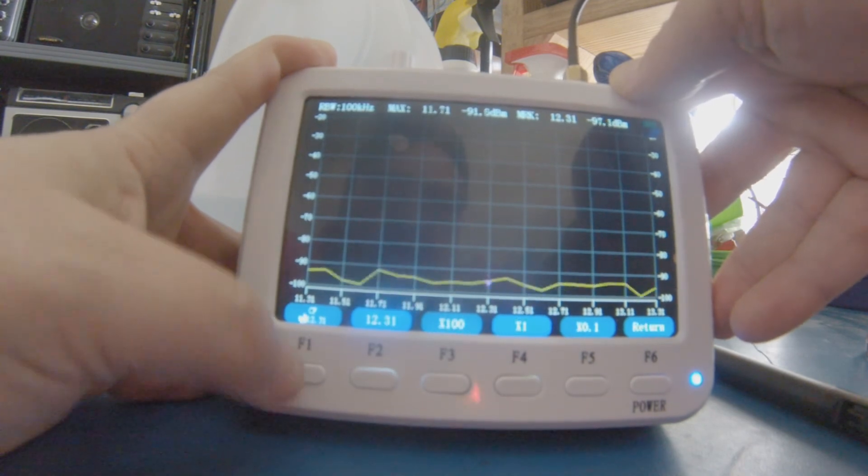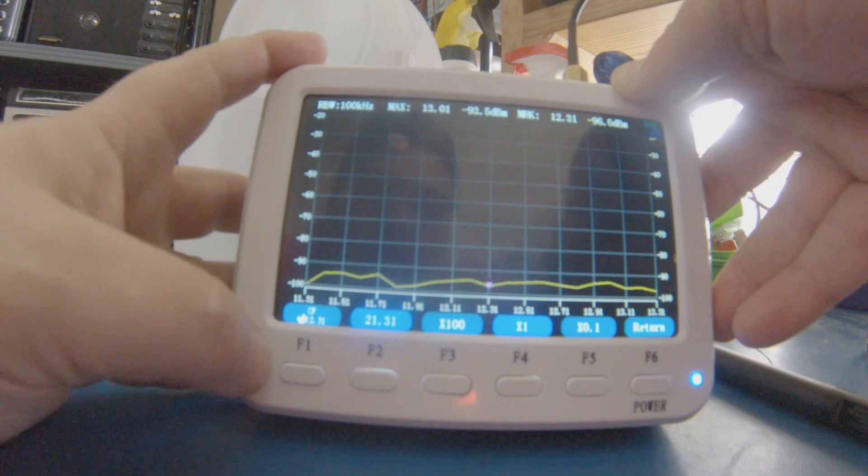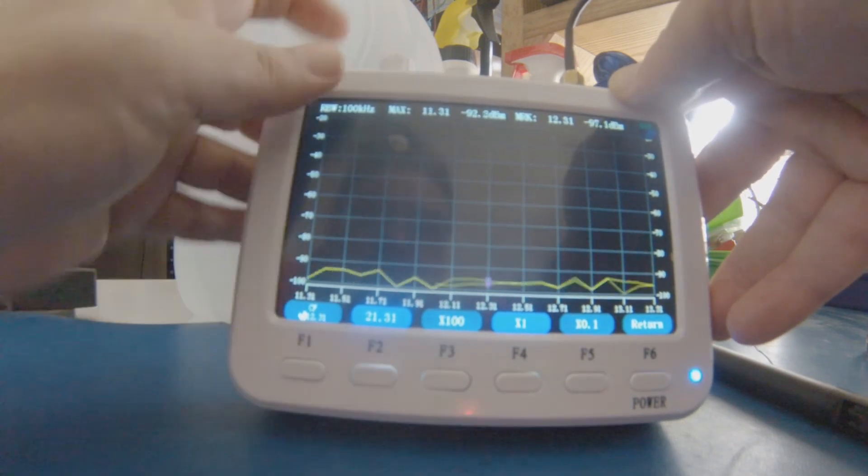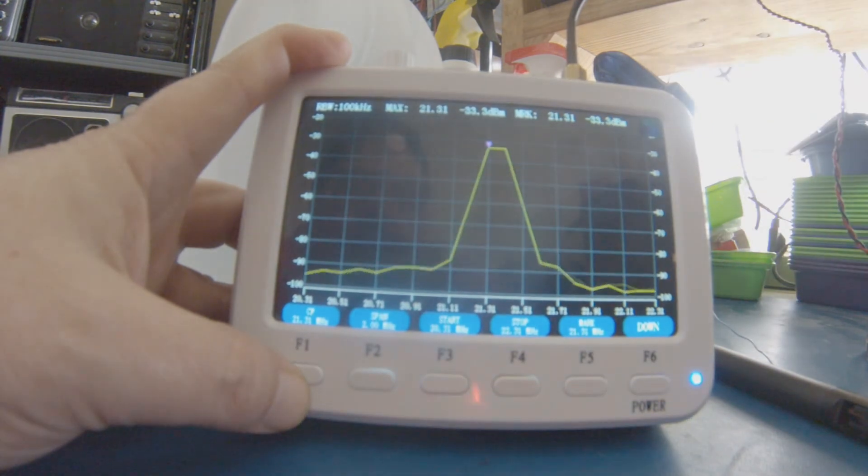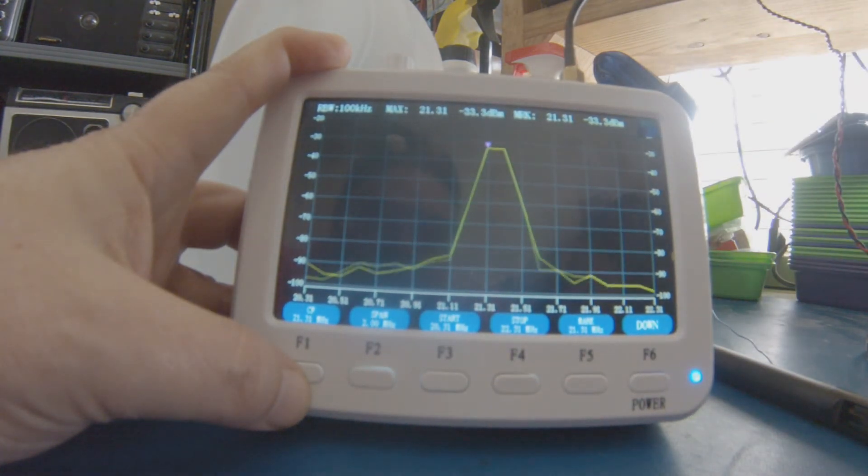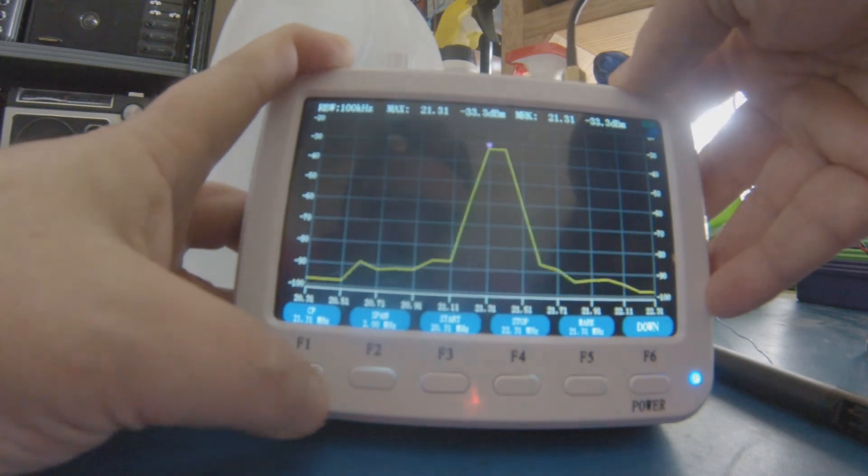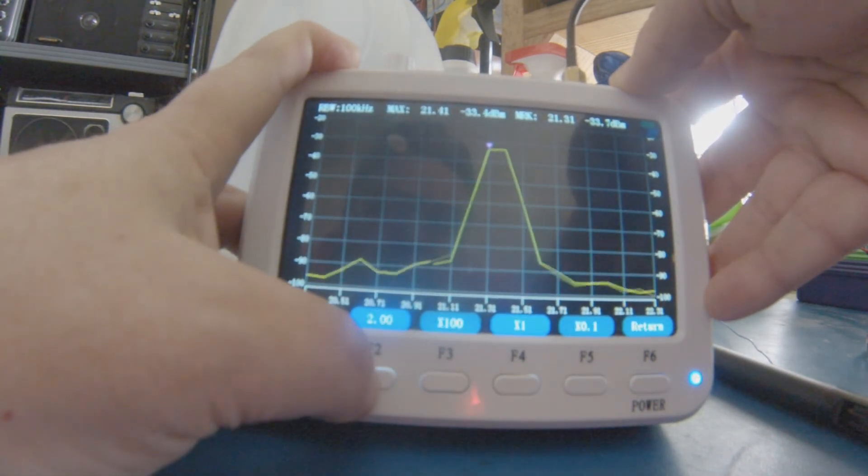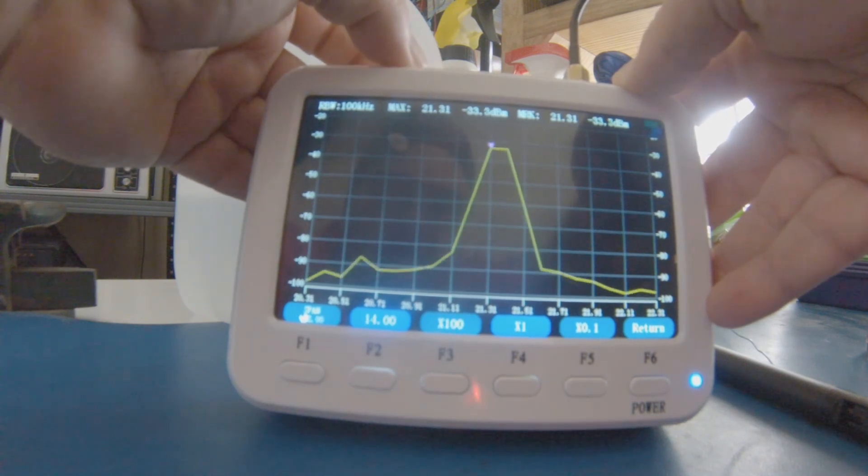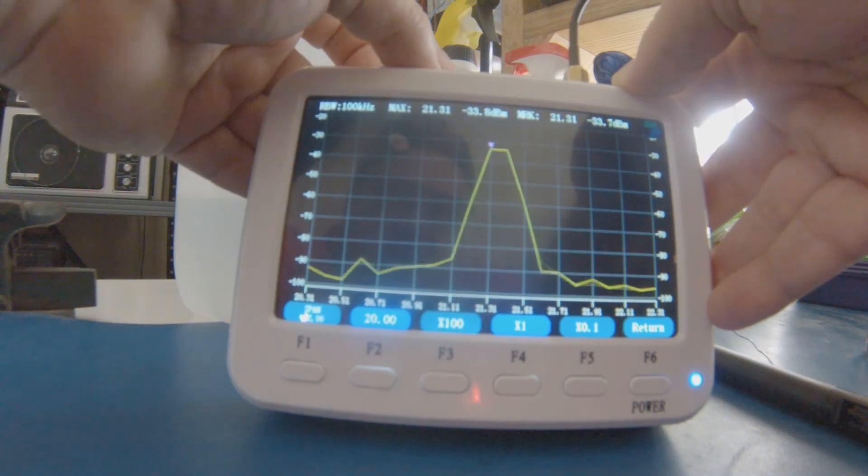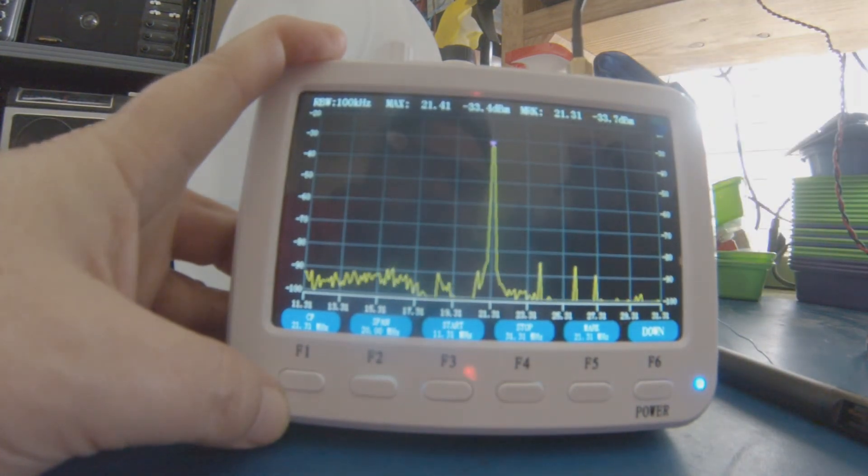I'm going back up to about 21 and hit the soft button. There's my peak, but my span is very narrow, so I don't have a lot of points of resolution on this. So I can go back to my span, make it back to 20 megahertz, and there's my peak back. It's pretty close to the marker again.